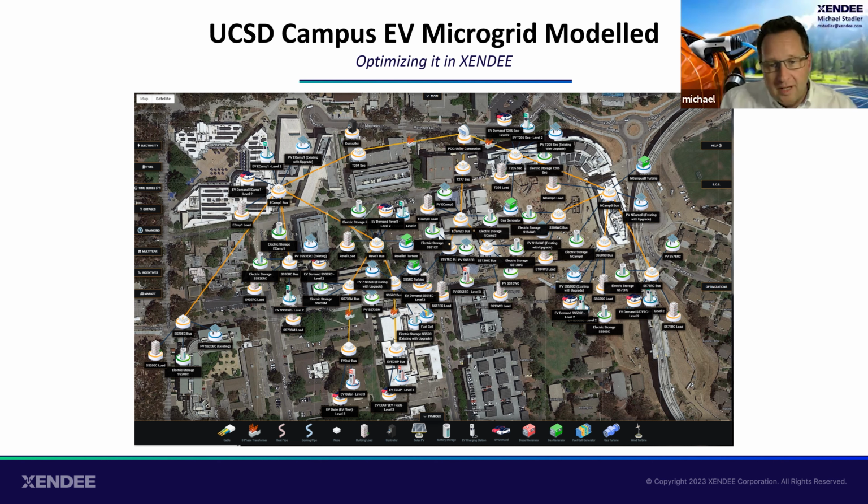Here, for example, we have transformers, and we already have existing distributed energy resources on our map here. The goal now is really to design the system at minimum costs to host additionally 40 DC fast chargers, and at the same time allow additional distributed energy resources at minimum costs at strategic places within the system so that we're not burdening the cables and transformers too much. And with this strategic analysis, we can actually add these 40 additional DC fast chargers and only have to upgrade a couple of cables and one transformer. And now I will talk you through this process.